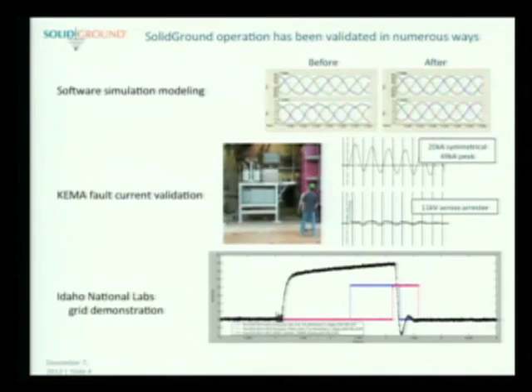We did ground fault testing in Philadelphia at the KEMA Labs, and we took, I believe it was 15 surge arresters through the pressure relief mode, and everything worked as planned. The surge arresters, after they've gone through that mode, have a resistance of about 2 to 10 ohms. So they're still conducting, even though they've gone into the pressure relief mode.